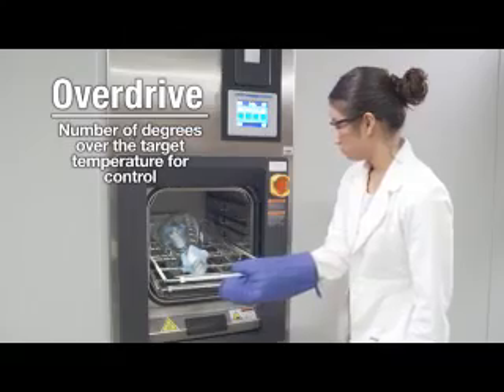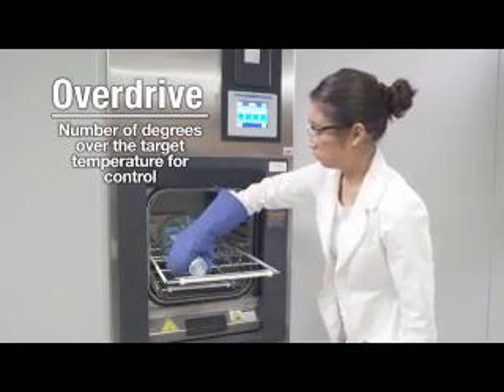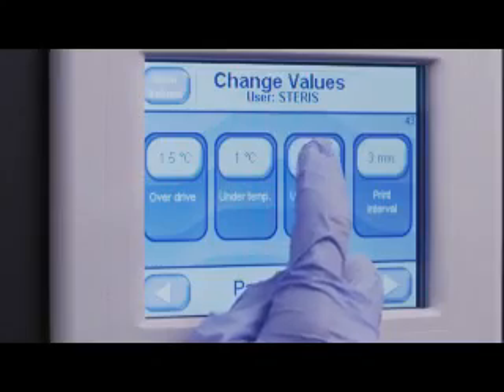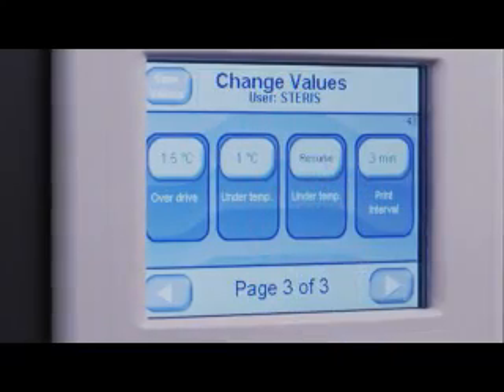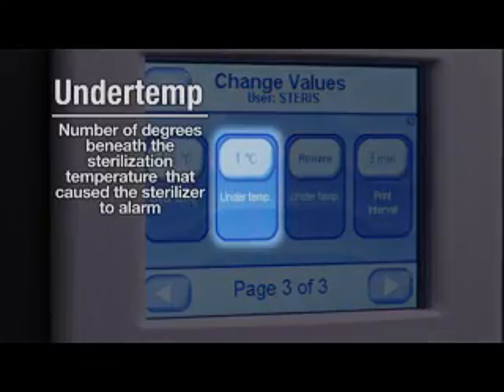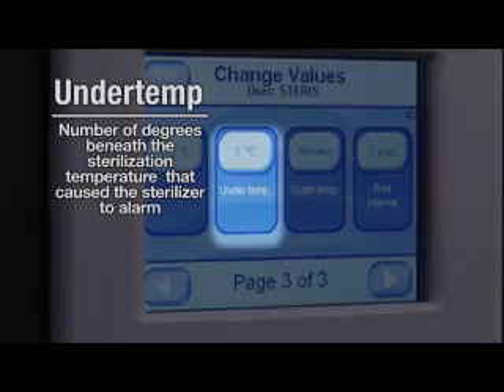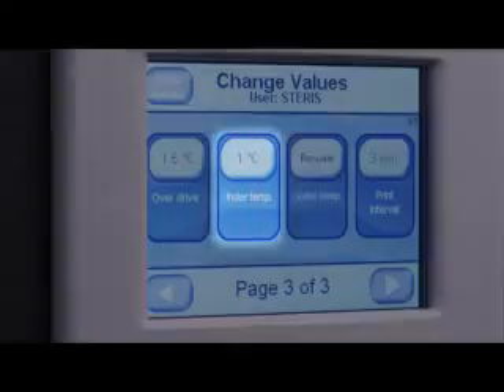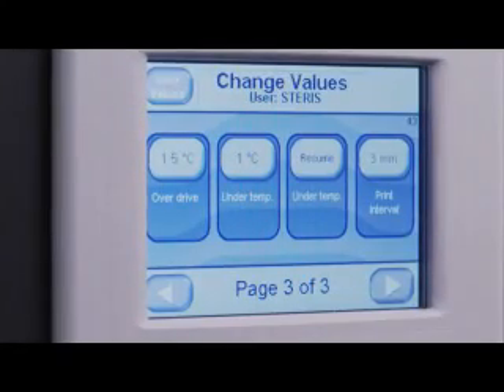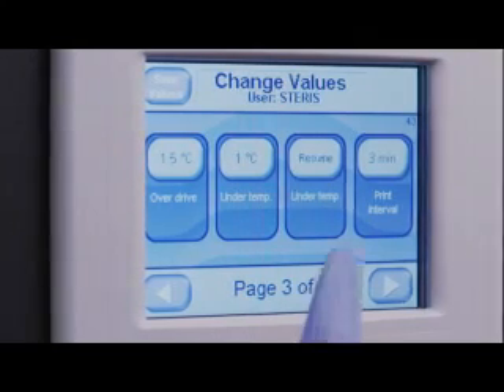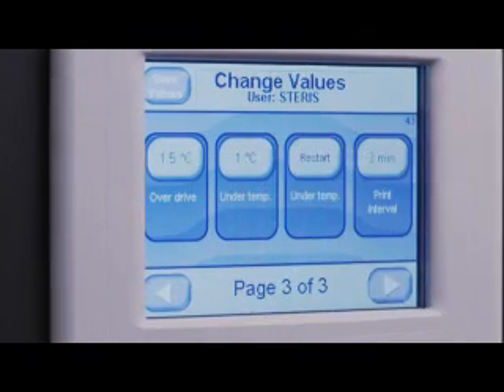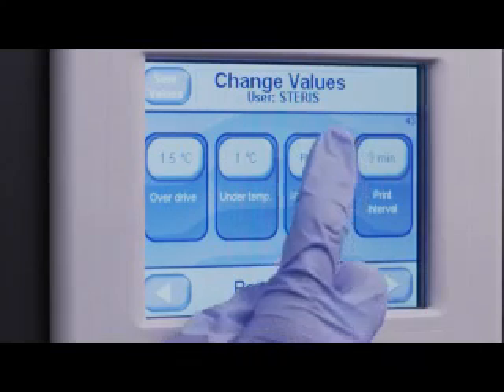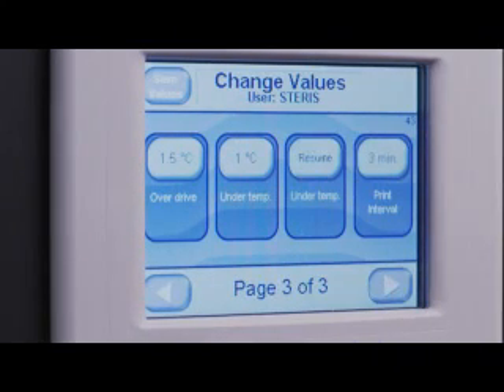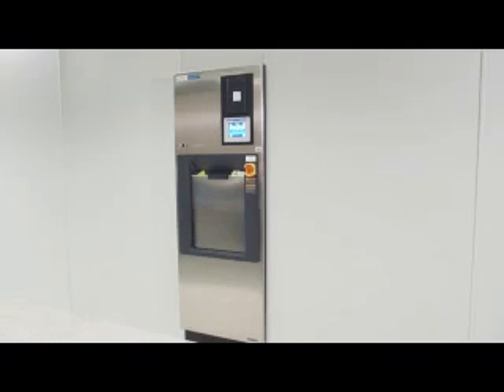This is a factory preset temperature that, in most cases, should not need to be adjusted. Should the temperature of the chamber drop below the set sterilization temperature, the under temp is the number of degrees below the set sterilization temperature at which the unit will alarm. Should the temperature drop below the under temp setting, the control can be set to either resume the cycle timer once the temperature has risen to the appropriate value, or the timer can be reset to begin the sterilization phase from the beginning.